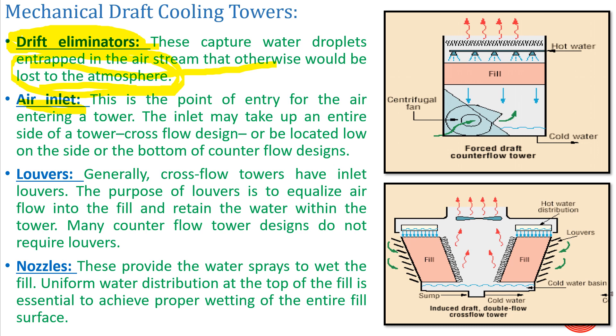Next is your air inlet. The air inlet depends on the type of cooling tower. In a cross-flow cooling tower, air enters from the louver sides, while in a counterflow force-draft tower, air enters from the bottom. The point of entry of air into a tower — the inlet may take up an entire side in cross-flow designs or be located low on the side or bottom in counterflow designs.